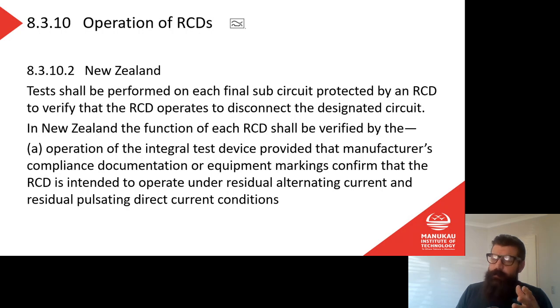Again, without going into too much detail, the RCD has an advantage over a circuit breaker because an RCD can trip at very, very low currents. It can pick up whether there's a small fault current in a circuit and it'll switch off. That small fault current in the case of RCDs in New Zealand is generally 30 milliamps. That's the requirement. So it must be able to detect a fault current of 30 milliamps, and it must switch off within 400 milliseconds, 400 milliseconds being 0.4 of a second. So a very tiny current switches off very fast.